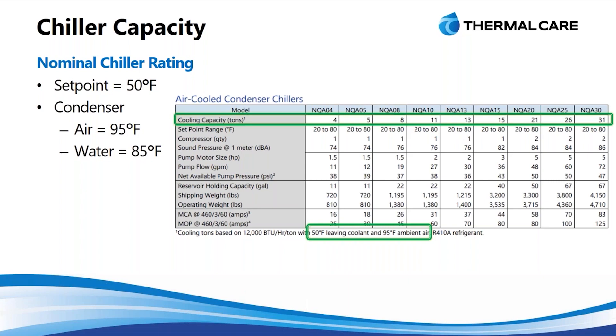The nominal rating is based upon a 50-degree leaving water temperature and 95-degree ambient air. In the case of a water-cooled unit, it would be 85-degree water. We'll talk more about the 95 and 85 and how we're cooling the condenser of the chillers later. The key point is that everything is being measured on a level playing field — so everybody rating a chiller, when they say a nominal chiller ton, they're using these same parameters.